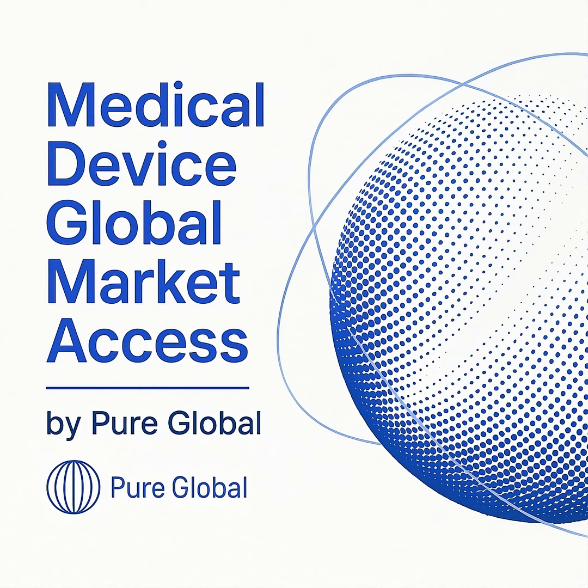South Korea's regulatory framework, governed by the Medical Device Act, shares a foundational principle with the FDA, a risk-based classification system. Devices fall into one of four classes, from Class 1, lowest risk, to Class 4, highest risk, which dictates the regulatory burden. This is where the paths diverge.